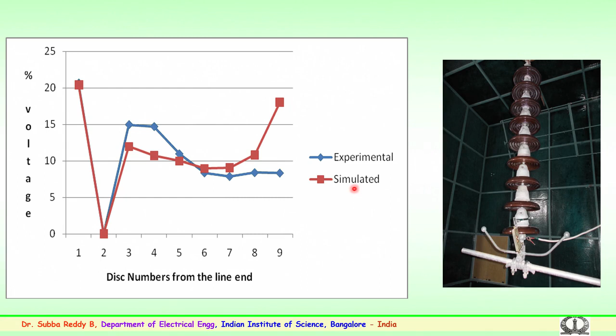These are some more experimental and simulated results in the laboratory for a 9 disc insulator string, where we have tried to see the failures, with faults intentionally created, and the study has been done. So, overall, when you look at the results for a 400 kV transmission system, when you take the defective insulator in case it happens to be in the second, third or fourth position from the line end, that is the high voltage end.